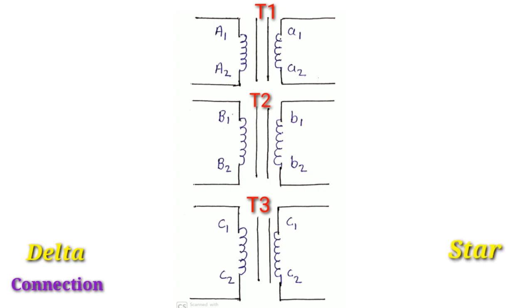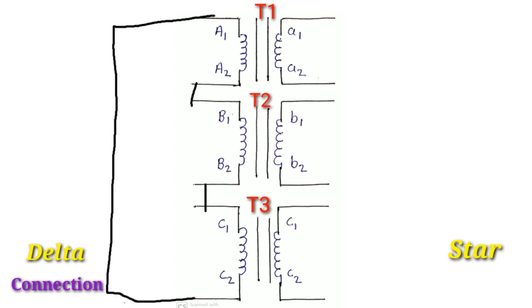Transformer T1 primary winding has two terminals a1 and a2. Terminal a2 is connected to transformer T2's terminal b1. Transformer T2's second terminal b2 is connected to transformer T3's terminal c1. Finally, transformer T3's terminal c2 is connected back to transformer T1's terminal a1. With this connection, the primary side is connected in delta.